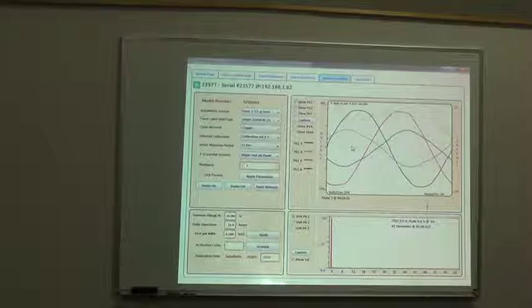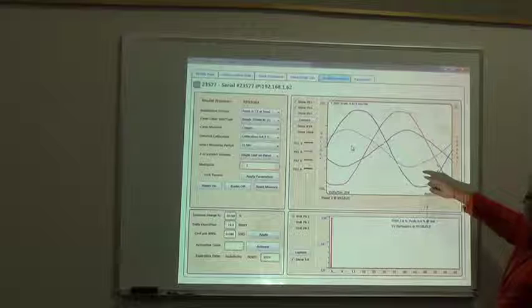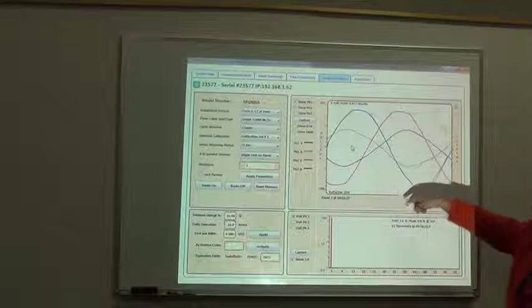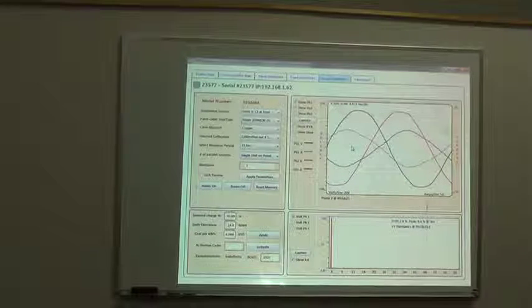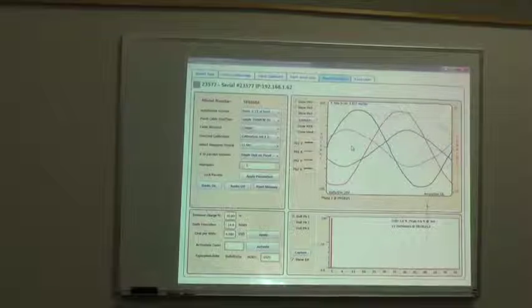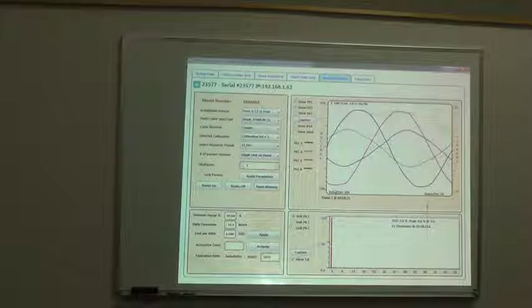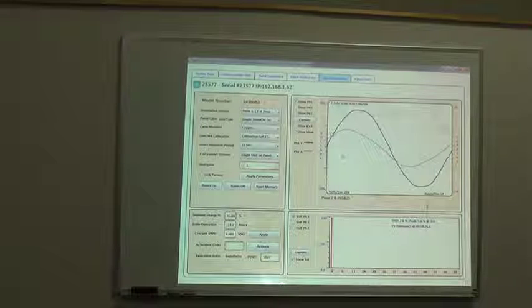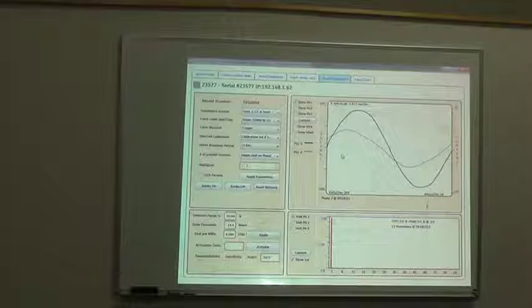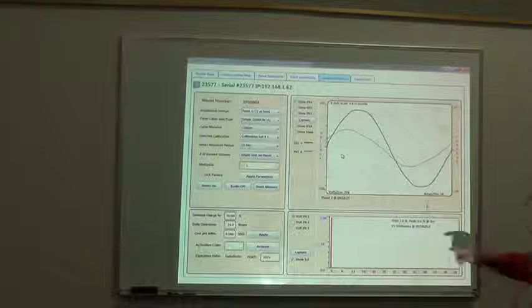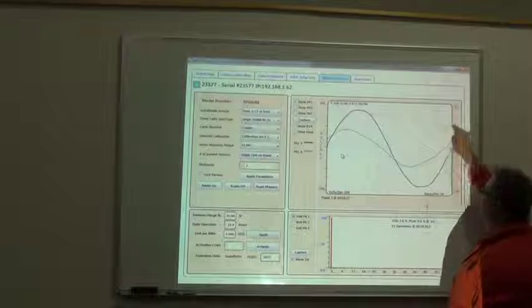That's the reason why I said that, because that's exactly what I saw when I looked at line code. You know what I mean? So, the other issue is that if I literally took this CT, and I purposely did this here, if I shut off phase 2 and only show you phase 1, it's easier to see that. Okay? If you can see, this is what a lagging power factor looks like, right?